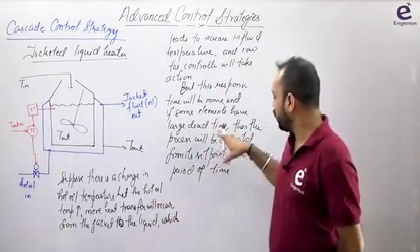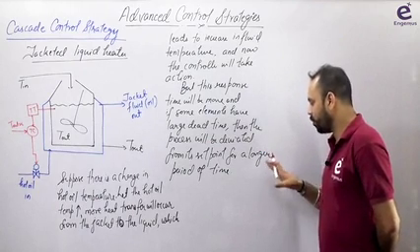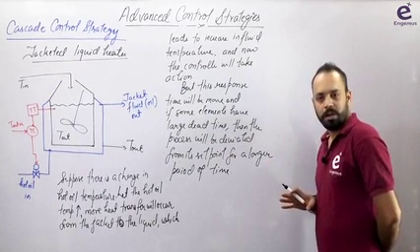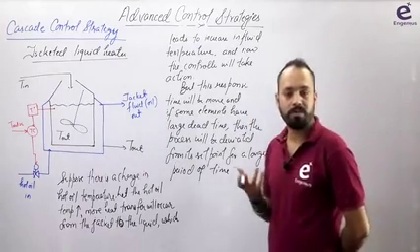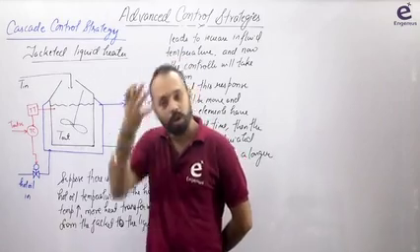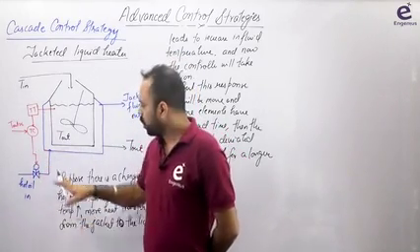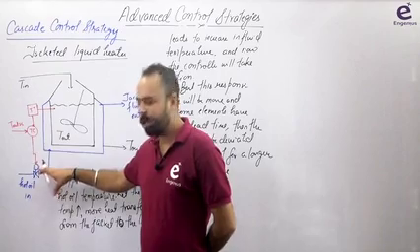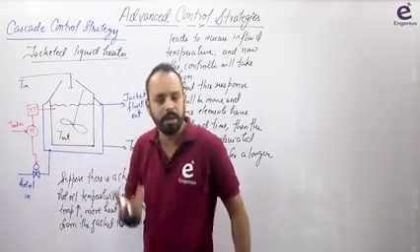But in the case if some elements are having large dead time, then the process will be deviated from its set point for a longer period of time, right? कुछ कंट्रोलर में भी कुछ डेड टाइम होंगे, कंट्रोलर के एक्शन में भी कुछ प्रॉब्लम्स हो सकती है. कंट्रोलर ने एक्शन तो लिया लेकिन उसको यहां तक पहुंचने में काफी टाइम लग गया. वॉल्व में कुछ सिचुएशन हो सकती है कि कंट्रोलर इज गोइंग टू चेंज दिस, राइट? नाउ दिस इज गोइंग टू चेंज दिस, एंड अगेन उसका असर होने में भी तो टाइम लगेगा ना यार.